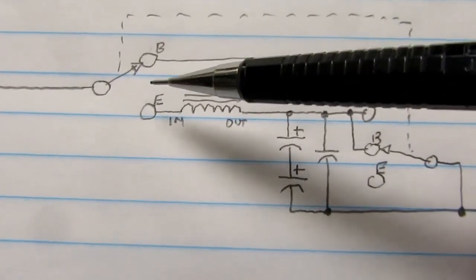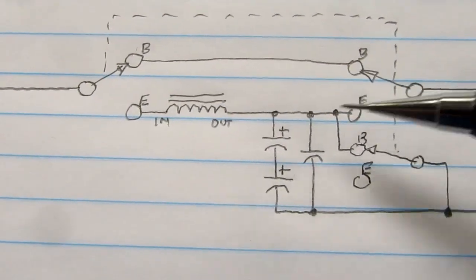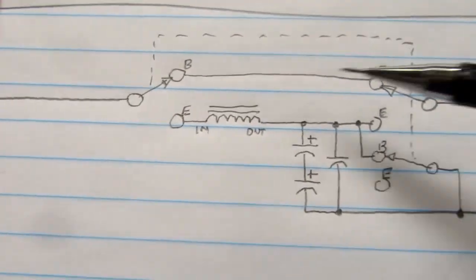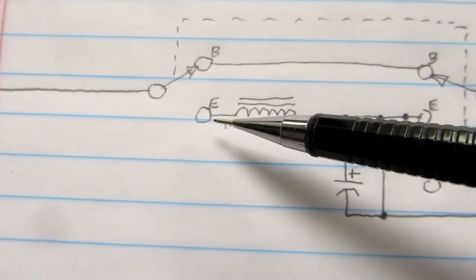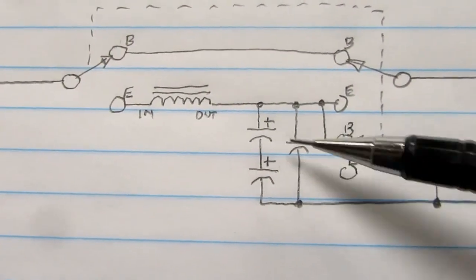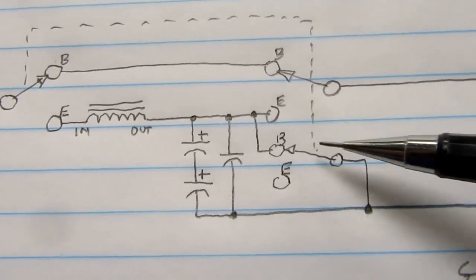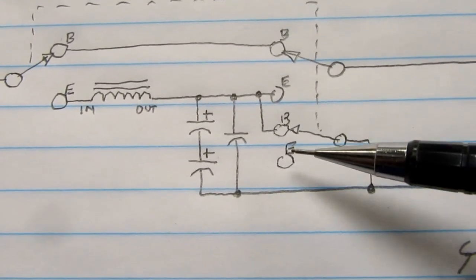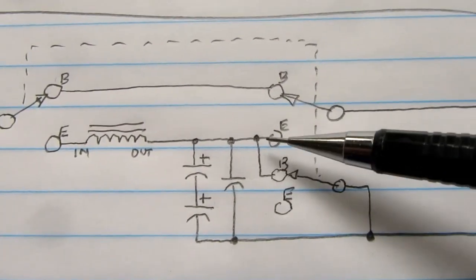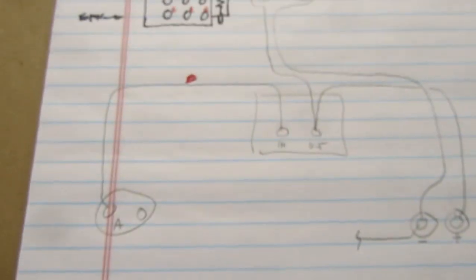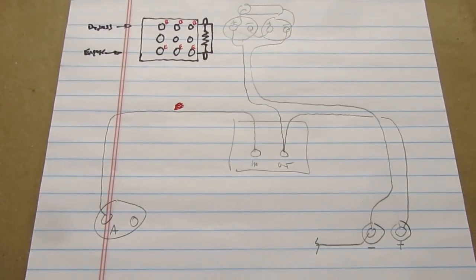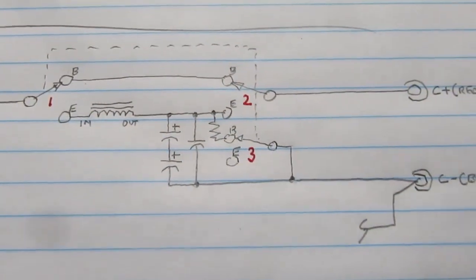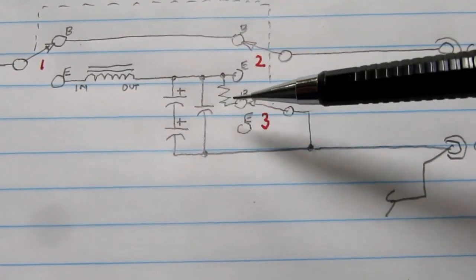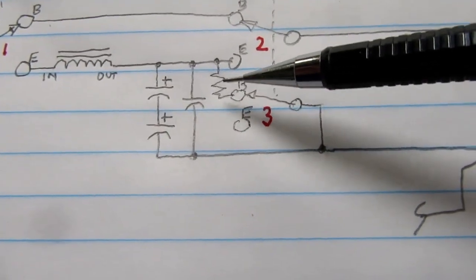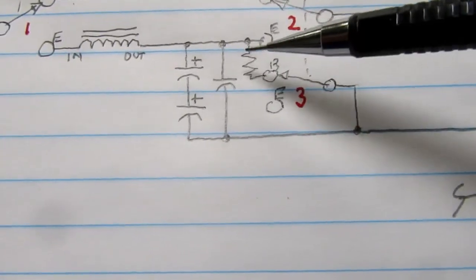Now when we move the switch to the engaged position, the bypass circuit is removed. We come from the ammeter, we come down through the inductor and with the capacitor to ground, and the shorting contact is opened up now, so the capacitors are no longer shorted. Then we continue on to the output. So pretty simple. I just need to come up with the most economical rewiring of this circuit. Of course, instead of just shorting out the capacitors, I'm putting in this resistor here so that the capacitors discharge through a resistance.